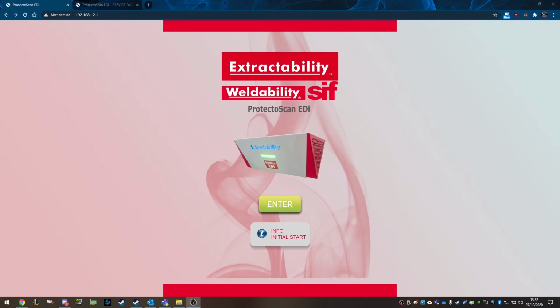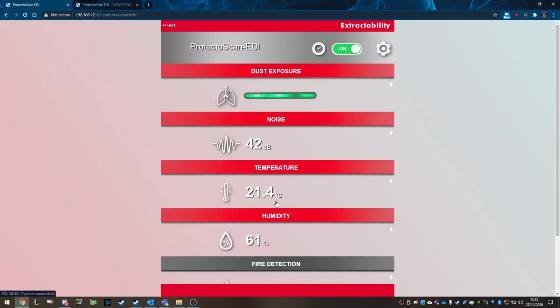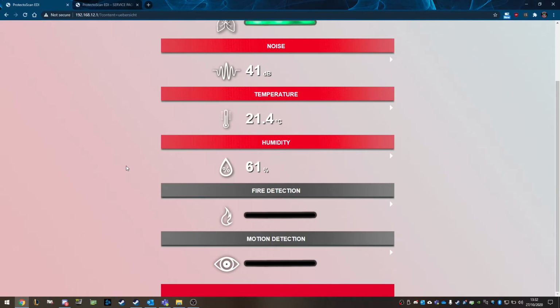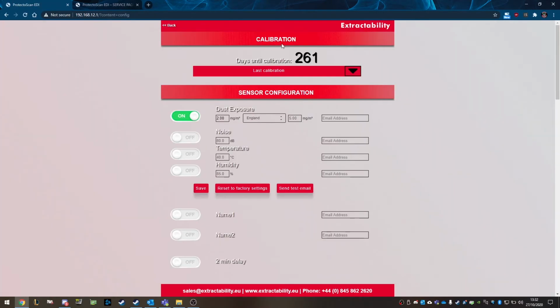So the first thing we're going to do is connect to our ProtectoScan EDI. This will either be on your wireless network or you'll be using it as a standalone device. We go into settings, and up here we can see the days until calibration. If this has got a minus setting, then you will need to either replace the sensors, or if the unit is brand new, then you'll need to get a service code from us to get it reset back to normal.